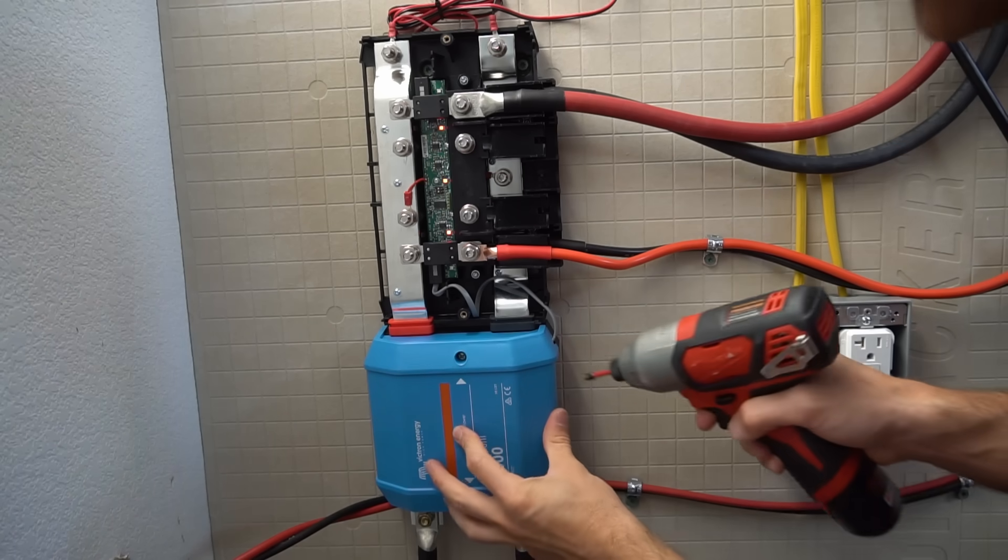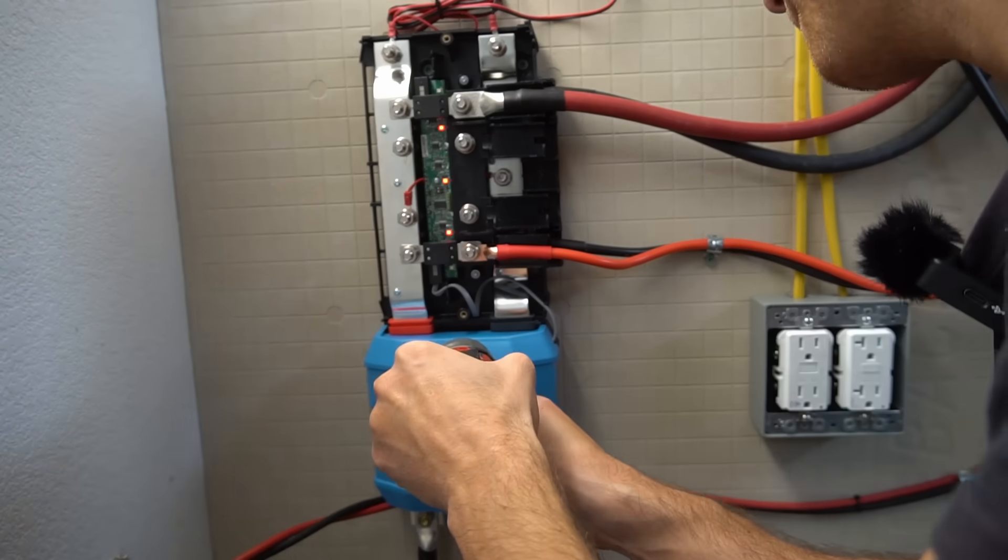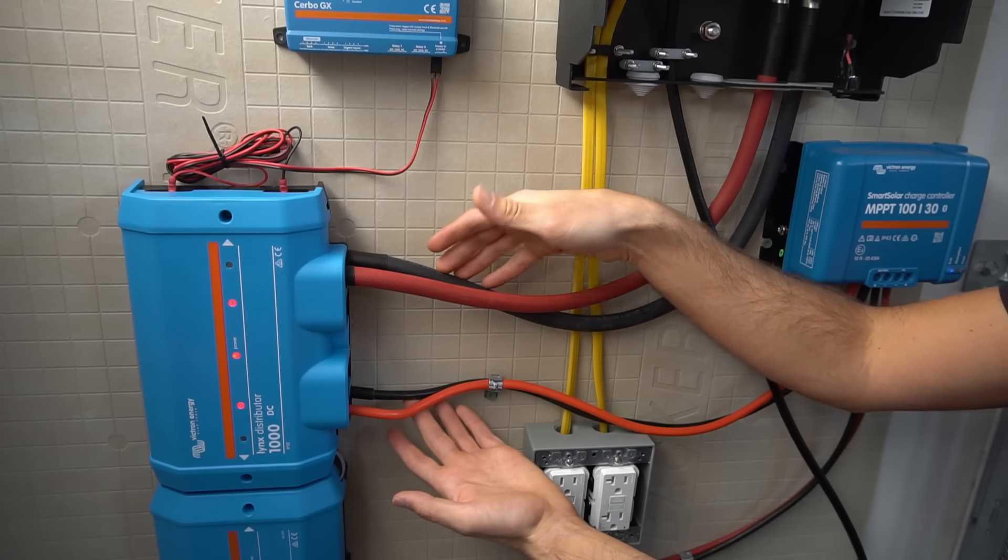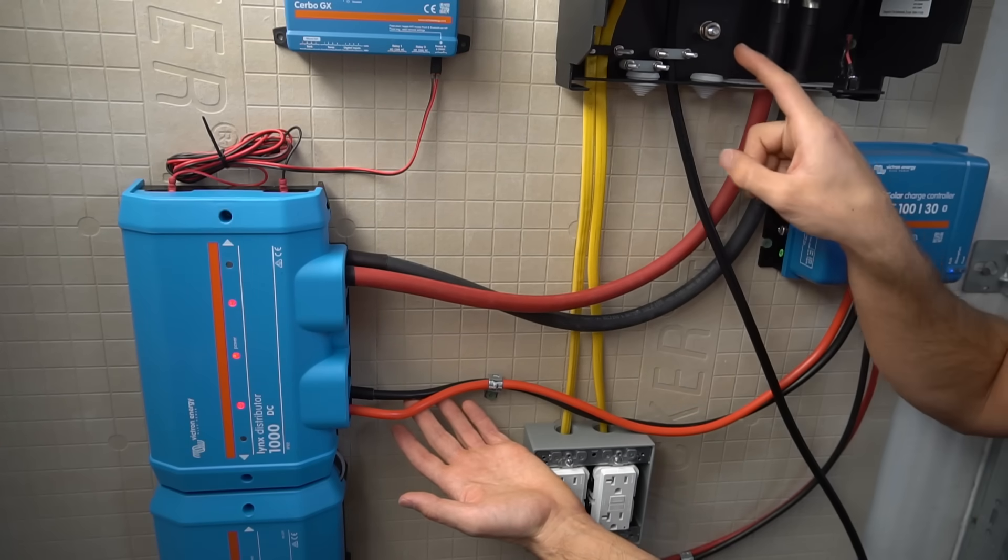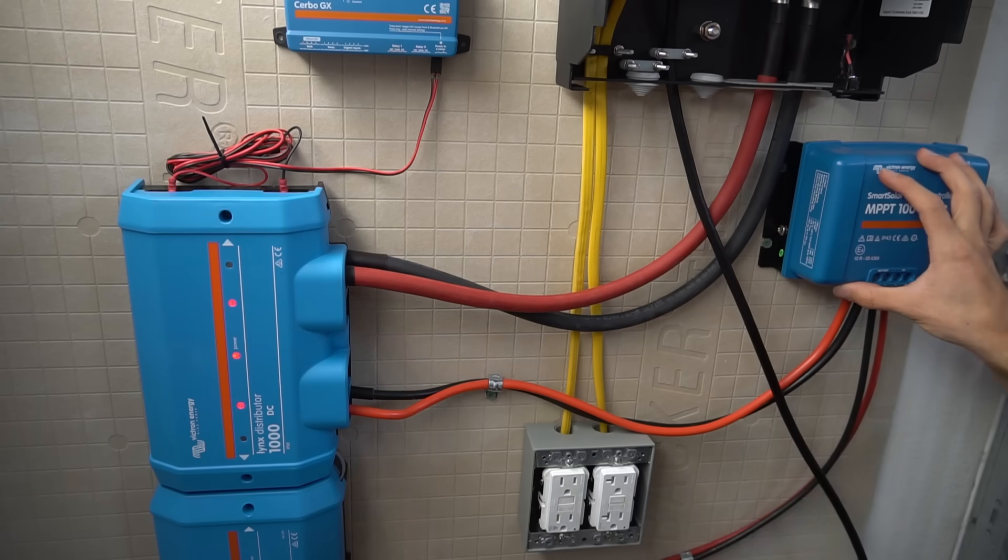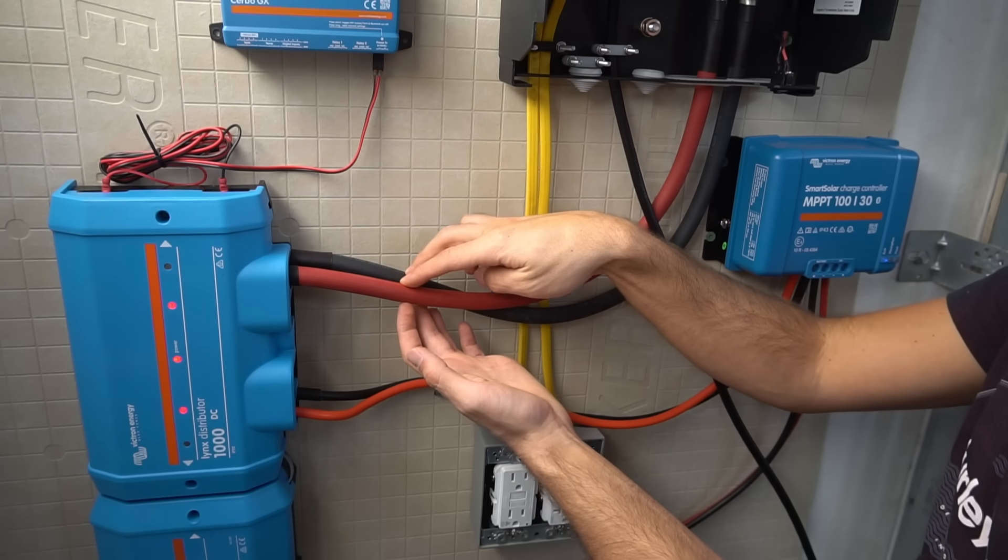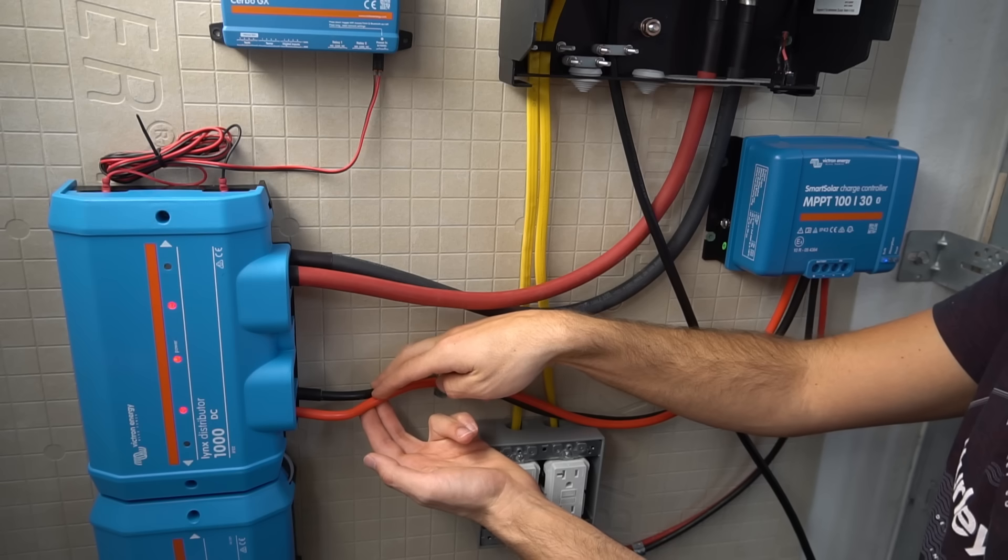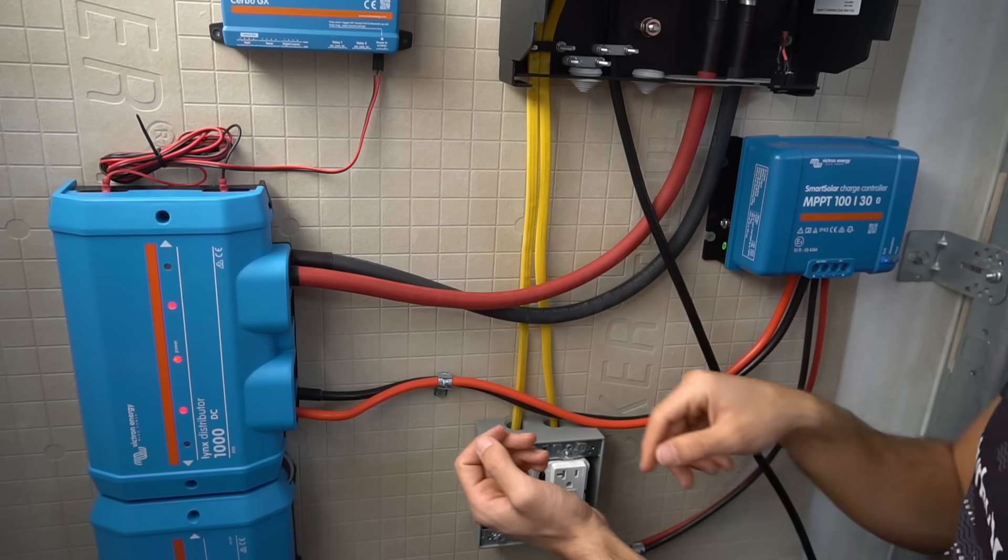Now these massive cables connect the distributor to our 12 volt inverter and also our solar charge controller. These cables have to handle 250 amps and these only have to handle 40 amps. So there's a massive size difference.